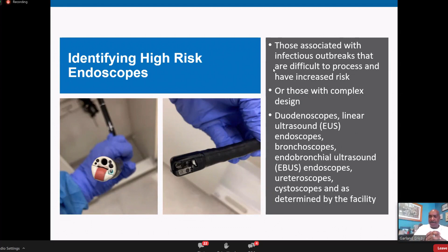Cleaning verification testing. Now, you definitely want to make sure that you are doing cleaning verification, in particular on those high-risk scopes. Again, you say shall be monitored with cleaning verification after each cleaning and prior to high-level disinfection or sterilization. Scopes that are not high-risk should be verified using cleaning verification when new endoscopes are purchased, and however you deem your percentage rate. So you may want to do 10% of your scopes. You may want to do 5%. You may want to randomly pull scopes from sterilization.